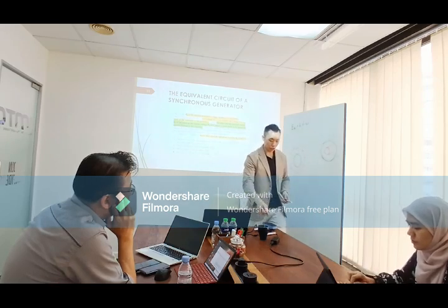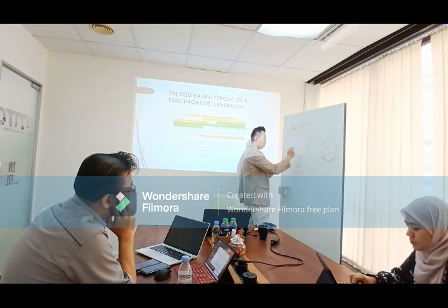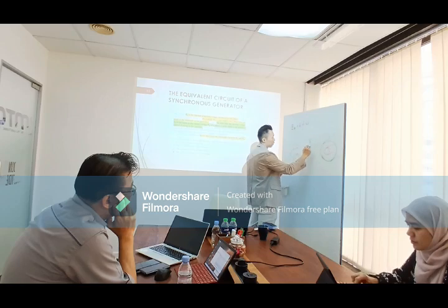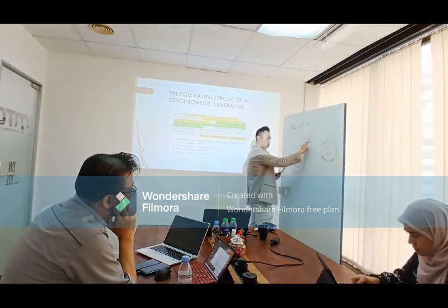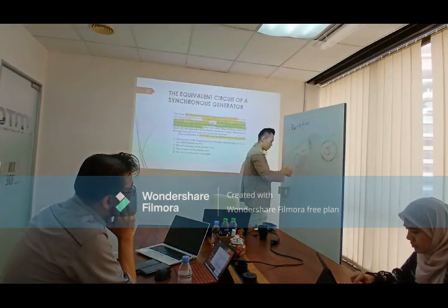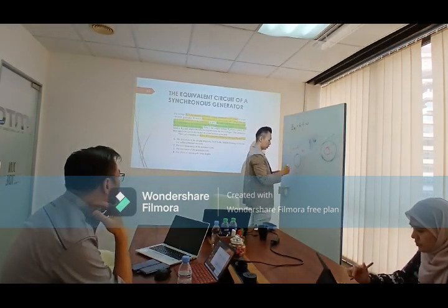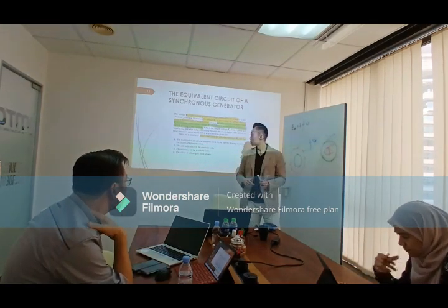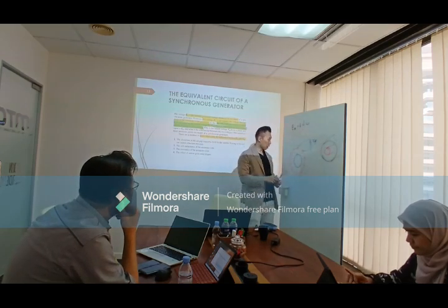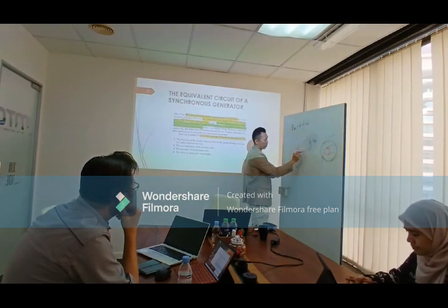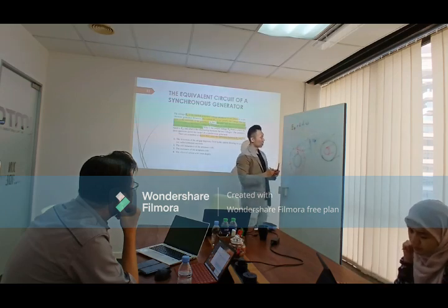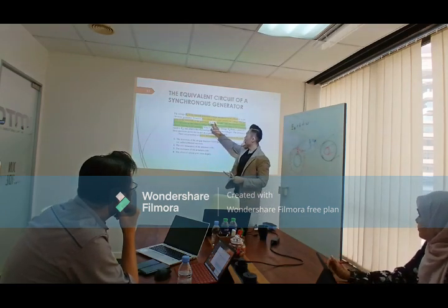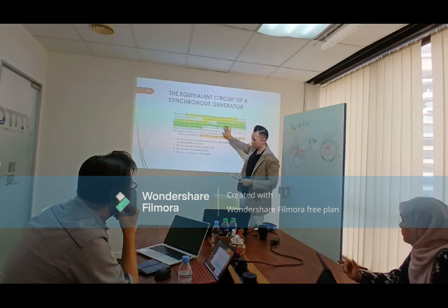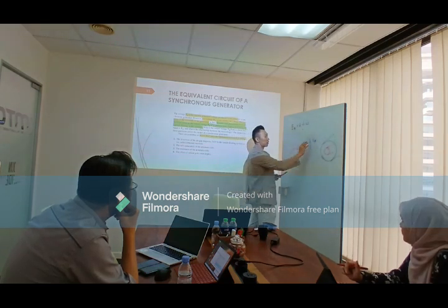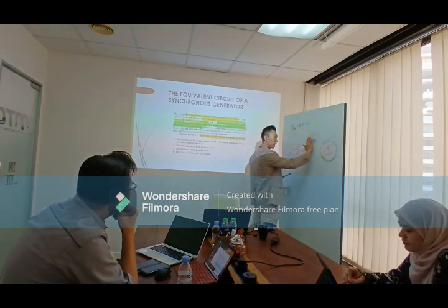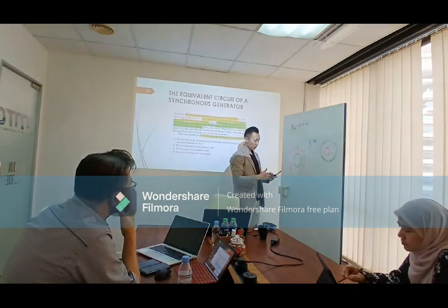The moment we connect to the grid, we have a particular load, and then you have a voltage drop. This is the voltage we call the terminal voltage, given by this symbol, and this other voltage at this point is what we call EA. So what this is saying is that if there's no load, then V phase and EA will be the same, of course.